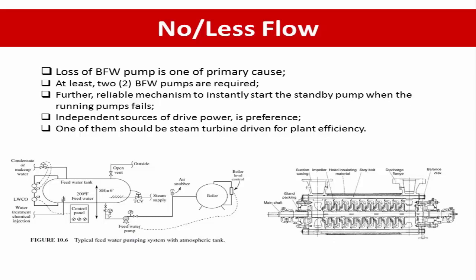With two boiler feed water pumps, there should be a reliable mechanism to instantly start the standby pump when the running pump fails. Boiler feed water pumps can be driven by an electrical motor or turbine, but considering plant efficiency, turbine driving is preferred.